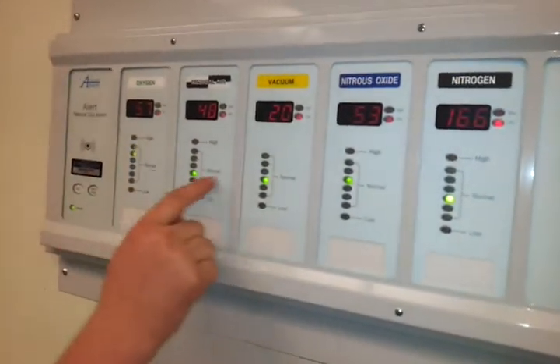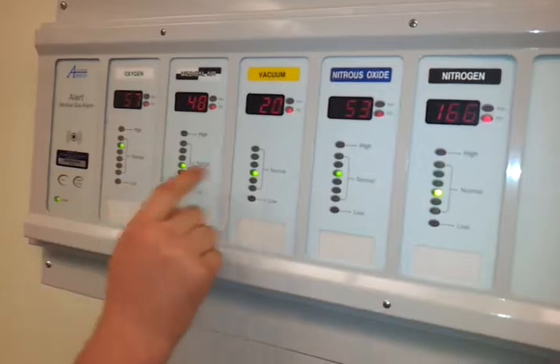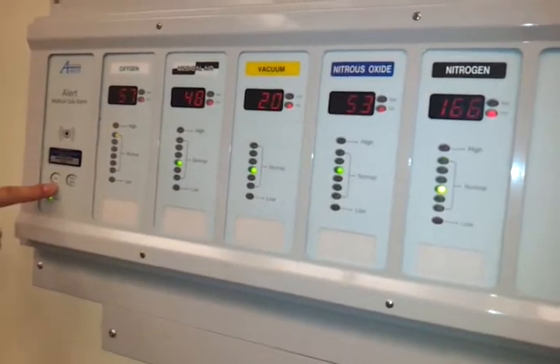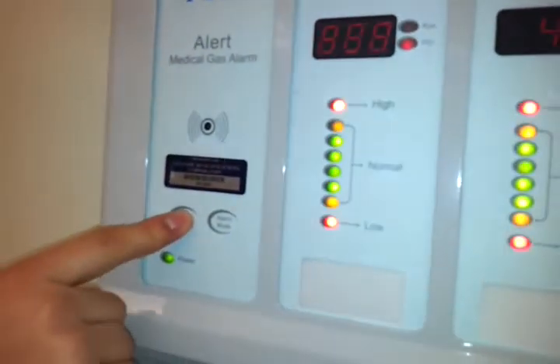The only other thing you have to check is on the wall back here, the medical gas alarms. You want all of these to be within the normal range. So basically you want them green. So to test it, there's a little test button on the side. Hit that, and yeah, they're all green. So we're good to go. So the 30 seconds is probably up.